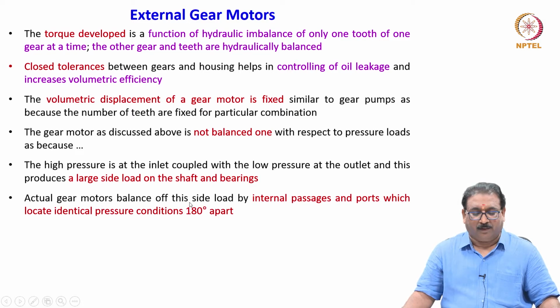Actual gear motors balance off this side load by internal passages and ports which locate identical pressure conditions 180 degrees apart.